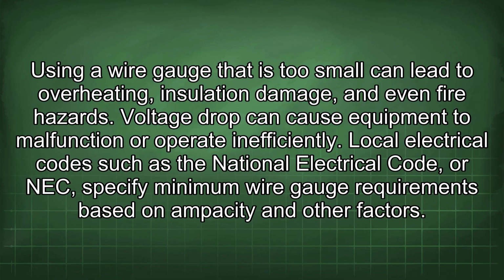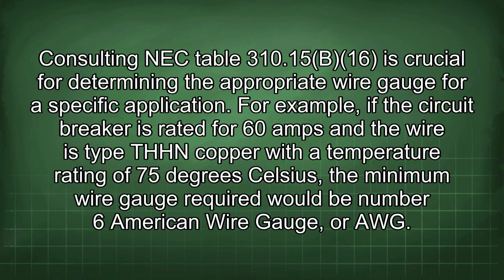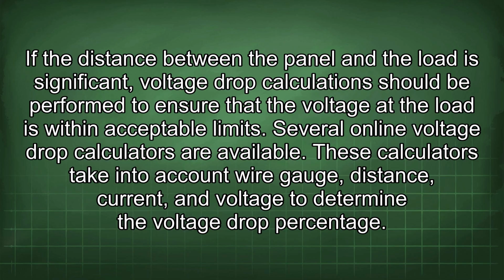Local electrical codes such as the National Electrical Code, or NEC, specify minimum wire gauge requirements based on ampacity and other factors. Consulting NEC Table 310.15(B)(16) is crucial for determining the appropriate wire gauge for a specific application. For example, if the circuit breaker is rated for 60 amps and the wire is type THHN copper with a temperature rating of 75 degrees Celsius, the minimum wire gauge required would be number 6 American wire gauge, or AWG. If the distance between the panel and the load is significant, voltage drop calculations should be performed to ensure that the voltage at the load is within acceptable limits.